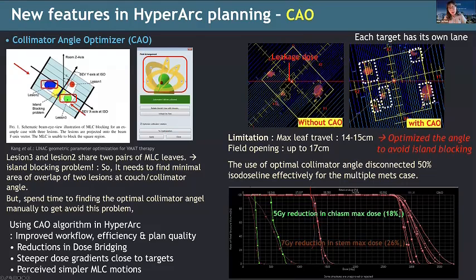The use of the optimal collimator angle disconnects the 50% or sometimes 30% isodose line very effectively for multiple-target cases. Here are the publications on the island blocking problem in multi-target cases with RapidArc. When you generate an SRS plan, you spend time finding the optimal collimator angle manually to avoid this problem, which improves the conformity significantly. But HyperArc already includes the CAO algorithm in Eclipse for your convenience.